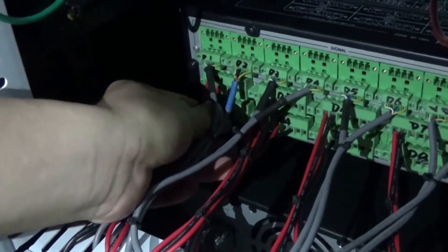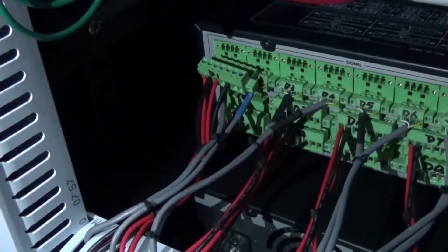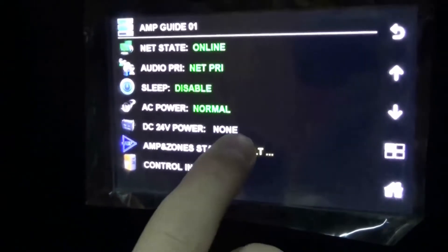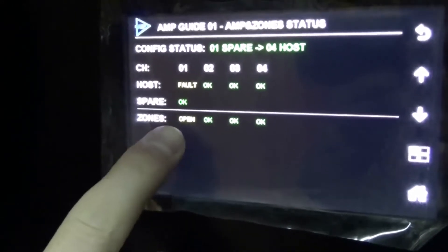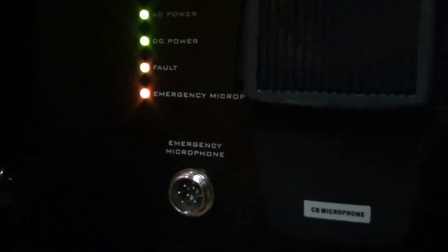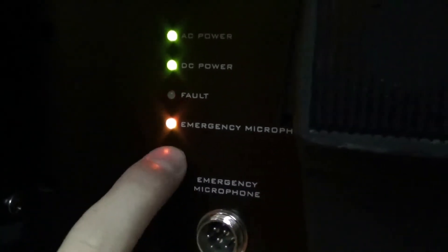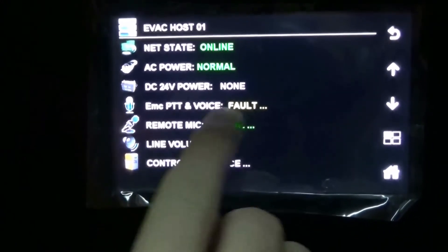Now I'm going to unplug the speaker output to simulate a speaker fault. We can see from here that something has gone wrong. From the front panel, we can check the zone status, and here we see the channel 1 speaker output has been opened. If you unplug the handheld microphone, you can see from here that it says the emergency microphone has gone wrong. And from the front panel, you can see that it says the handheld microphone has failed.